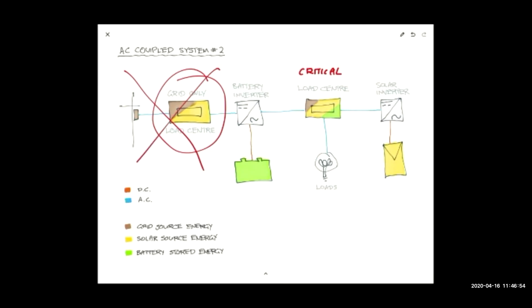If the grid fails, in this configuration using a special inverter—there are many brands of them, but it's not a normal feature of every inverter—it can accept power flowing from the solar inverter and send it back into the battery on its backup port. This is more typical of off-grid inverters, which have this feature, even though many off-grid inverters can also be used on-grid. So this is AC coupling with a load port, as opposed to on the grid side, and it allows the system to charge batteries from the solar even when the grid's not available.